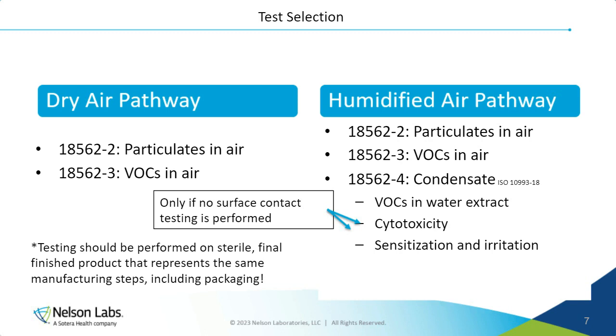If no surface contact testing is performed on the device, then the big three, cytotoxicity, sensitization, and irritation, will need to be tested. All of this testing should be performed on a sterile, final finished product that has gone through all of the applicable sterilization and packaging steps. There are some cases where R&D can be done on the device that's not in its final finished form. That's why it's R&D. However, when submitting to regulators, it is expected that the final finished product be tested for the submission.